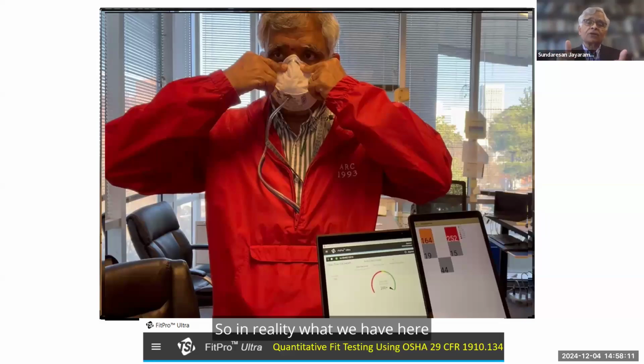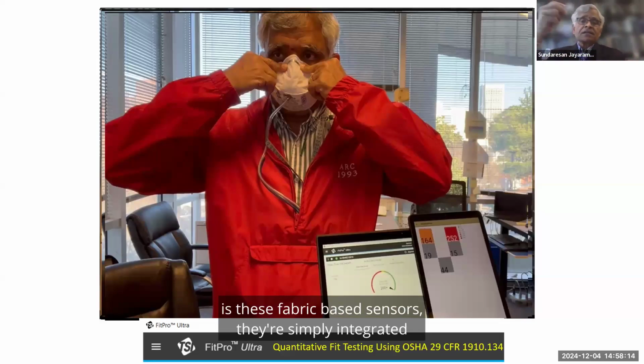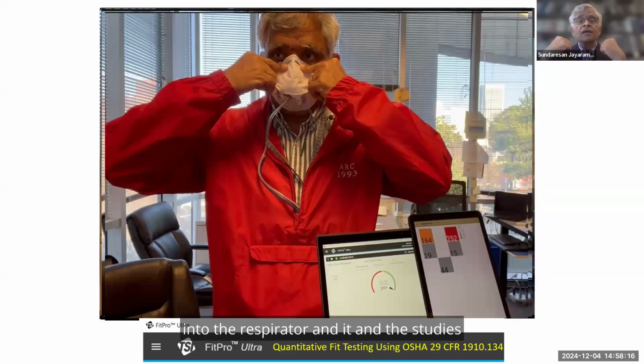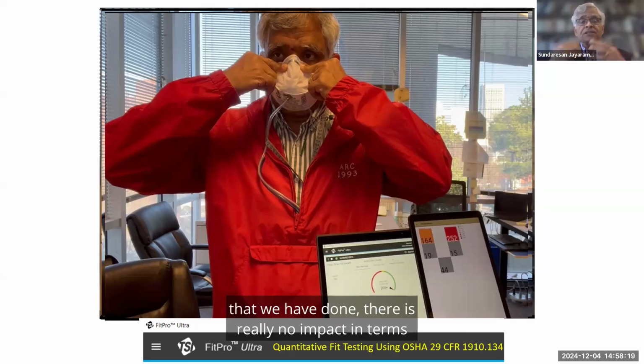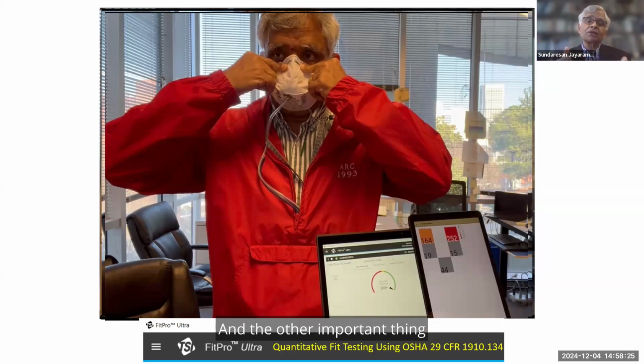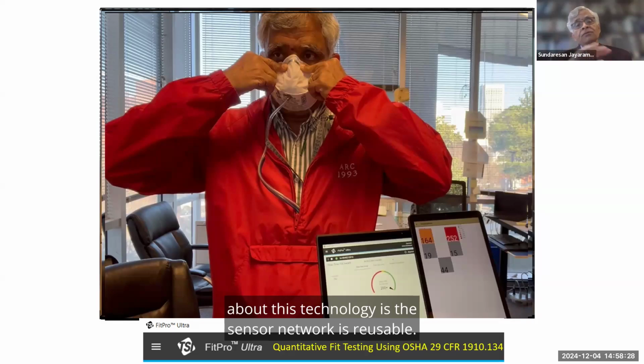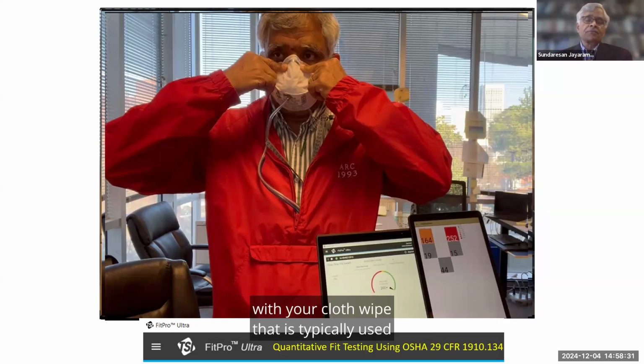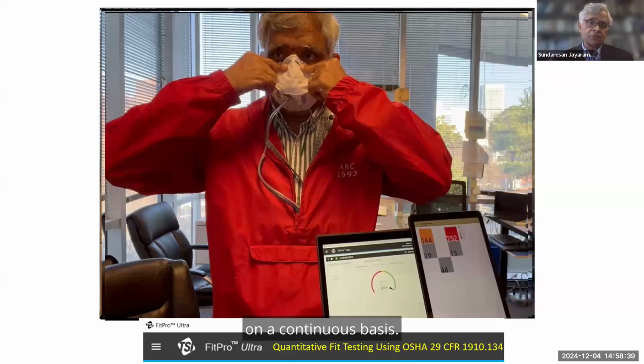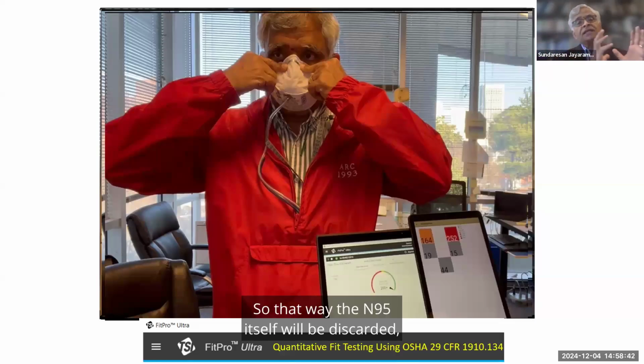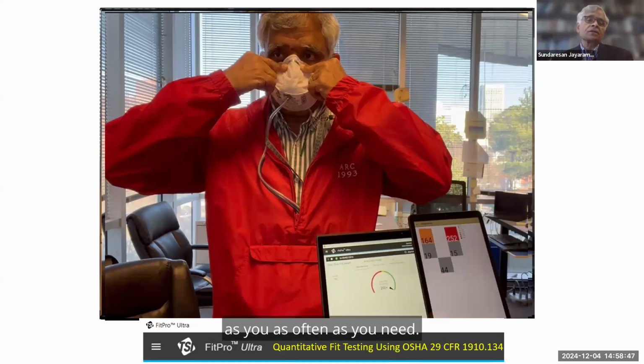So in reality, what we have here is these fabric-based sensors. They are simply integrated into the respirator, and in the studies that we have done, there is really no impact in terms of leaving any impressions or anything. And the other important thing about this technology is the sensor network is reusable. We can just wipe it off with the sani-cloth wipe that is typically used for decontamination, and then you can put it on the next device and use it on a continuous basis. So that way the N95 itself will be discarded, but the sensor network will be used as often as you need. Then the final slide, please.